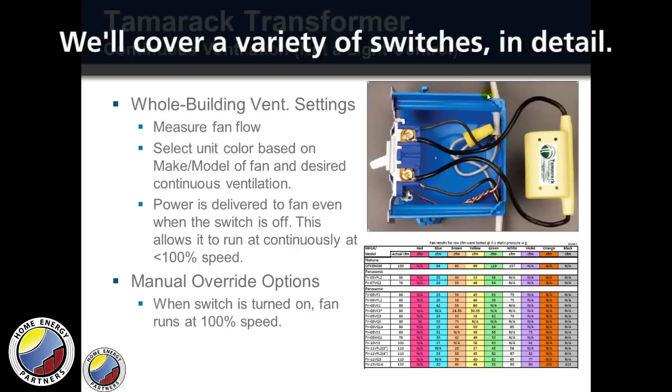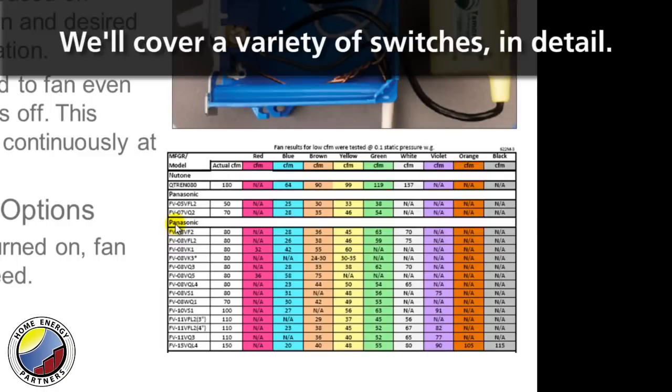They have a series of charts here that is broken down by the make and model of fan. So let's say that you were going to use this fan right here, the FV08VQ3. The actual CFM is 80, and maybe for your building you only needed 30 CFM of continuous ventilation.